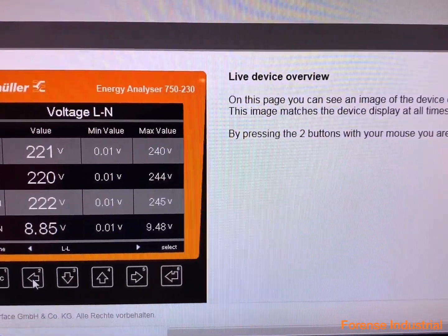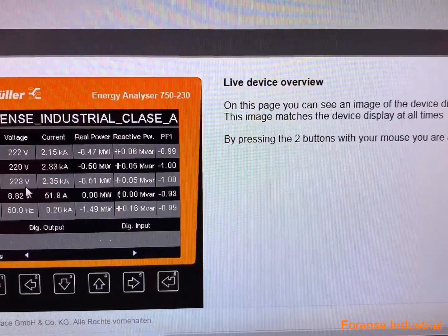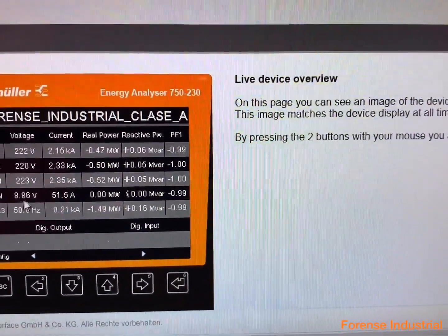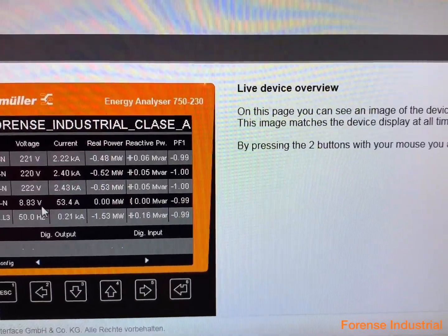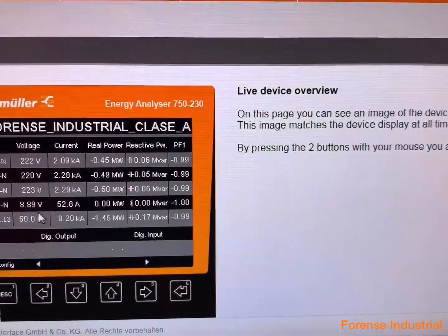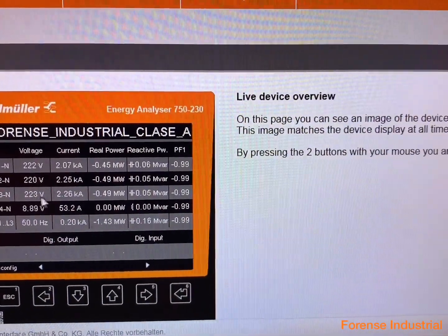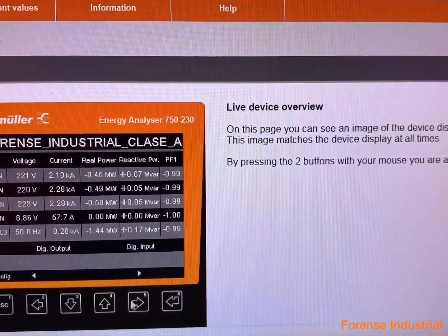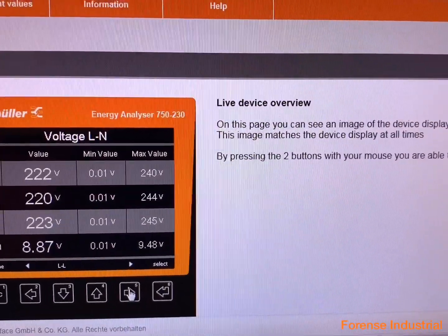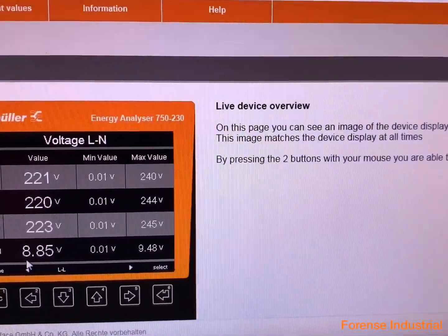Here you can see voltage, and this is very important. We have voltage in the neutral. It's very bad data for our final user, and we need to explain the reason and solve it, fix it as soon as possible. This is not a good one. Okay.